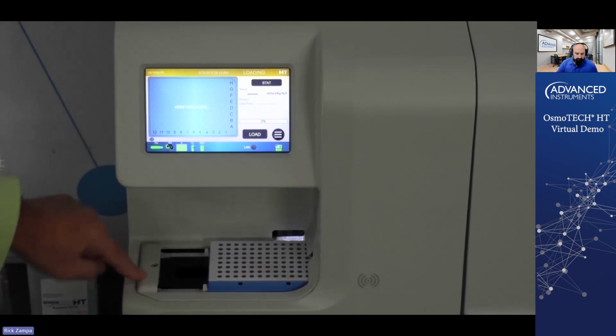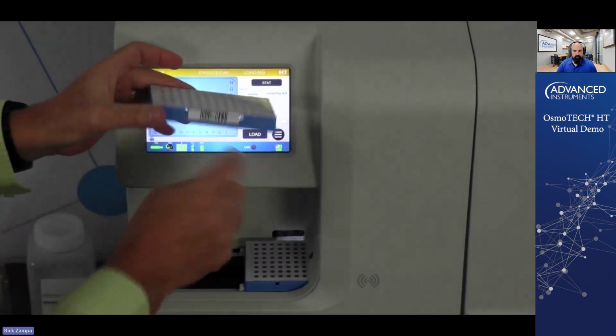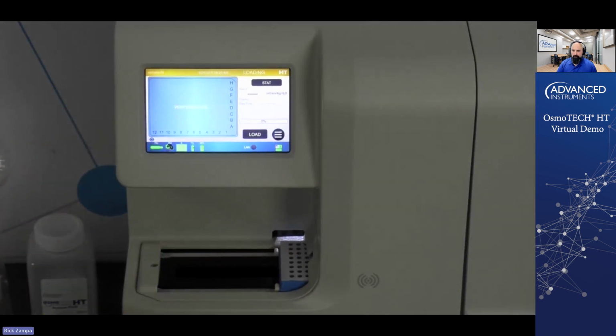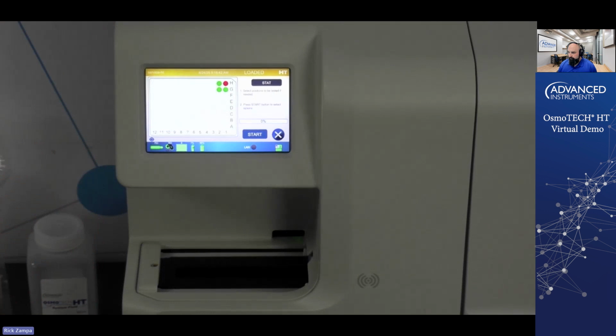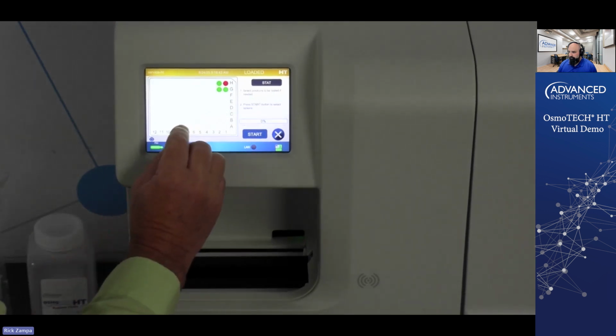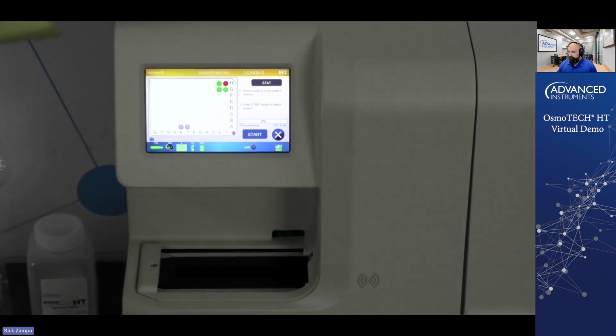The instrument is going to move the plate in. There's a barcode on the back side of the plate that the instrument is going to read. That's used to assure that you can use the whole plate. By reading that barcode, it tells me which positions on the plate have already been used or haven't been used, and then I can choose the ones that are open for my next testing. So it's verifying the plate, reading the plate. Once it's done that, it's going to bring up what we call a template. I'm going to choose the positions that I want to run, which I've loaded in, oops, not 9, 7, and 8. Now you can see here, it shows that those positions were already used.